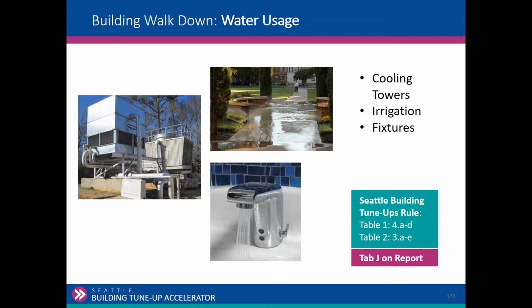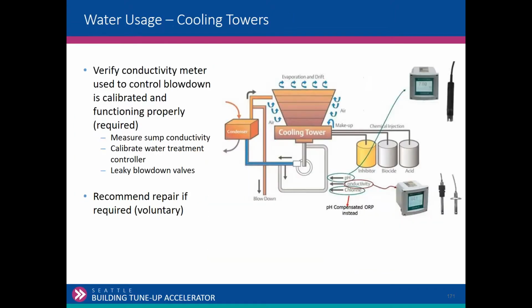On the water usage side, there are kind of 3 areas to look at. Cooling towers, so on water-cooled systems or hydronic heat pumps, you may have a cooling tower; irrigation; and fixtures themselves. On the cooling tower side, I'm going to get my slide because I wrote some notes here. The only function that is a required measure is to calibrate and control the blowdown. Pretty much most cooling towers use conductivity to determine when to remove water from the sump to add fresh water to dilute the mineral concentration in the sump. That conductivity uses a conductivity sensor. And so, is it calibrated?